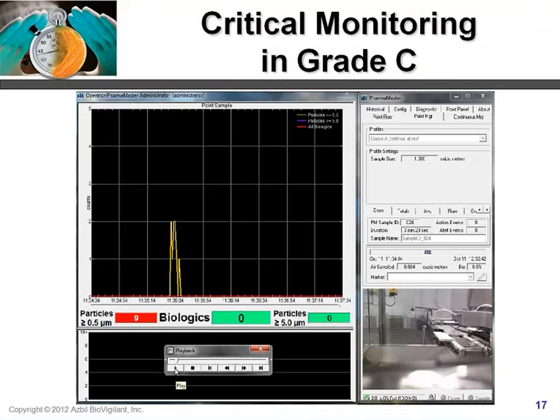So again, we're looking at a historical sample from all the testing that was conducted of the automated bag removal equipment. And you can see in the video that there's bags or tubs coming down the line, and then a tray comes over them and removes the bag and then pushes it through that interface from the grade C to the grade A area.